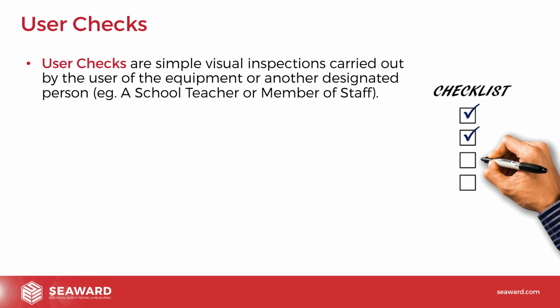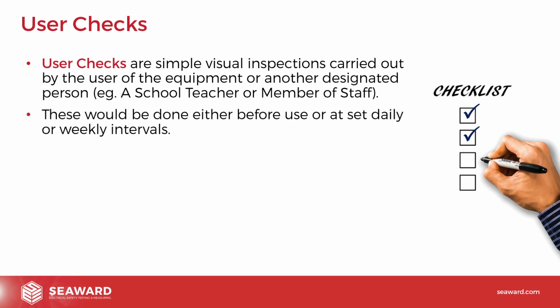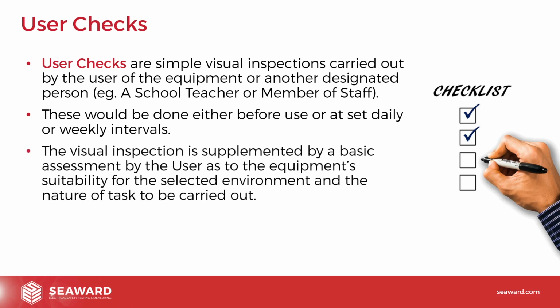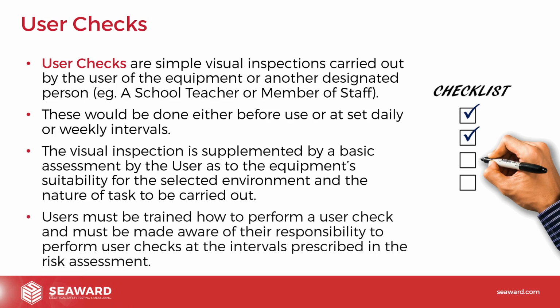So user checks. User checks are simple visual inspections carried out by the user of equipment or another designated person, e.g. a school teacher or a member of staff. These would be done either before use or at set daily or weekly intervals. The visual inspection is supplemented by basic assessments by the user as to the equipment's suitability for the selected environment and the nature of the task being carried out. So they wouldn't just look at the equipment; they're asking, is it suitable for the job I want to do with it? Is it suitable for where I want to use it? Users must be trained how to perform a user check and must be made aware of their responsibility to perform user checks at the intervals prescribed in the risk assessment.